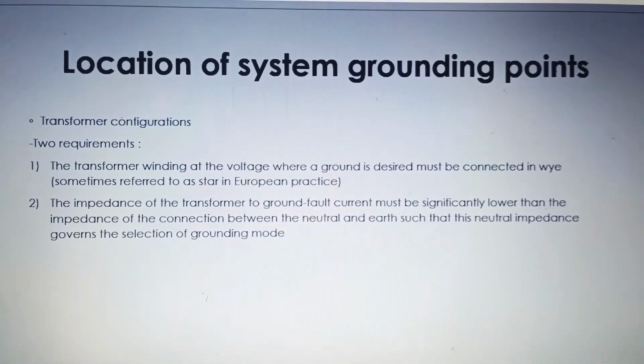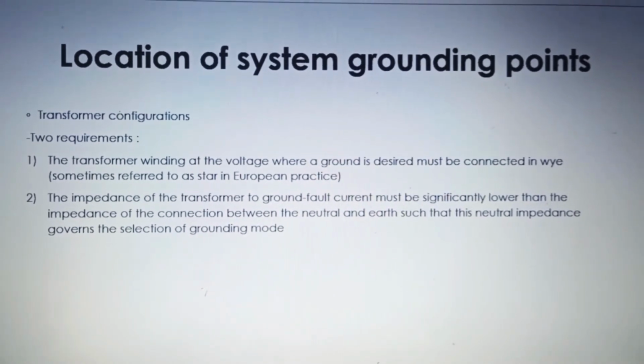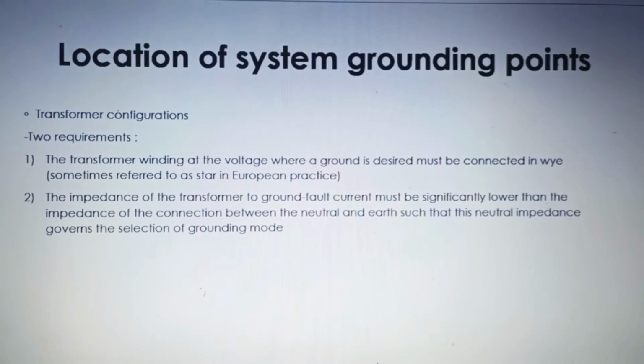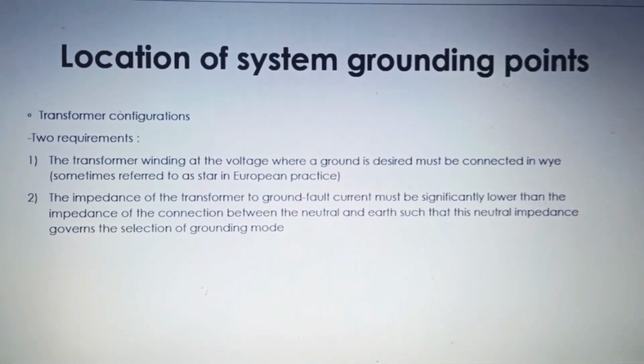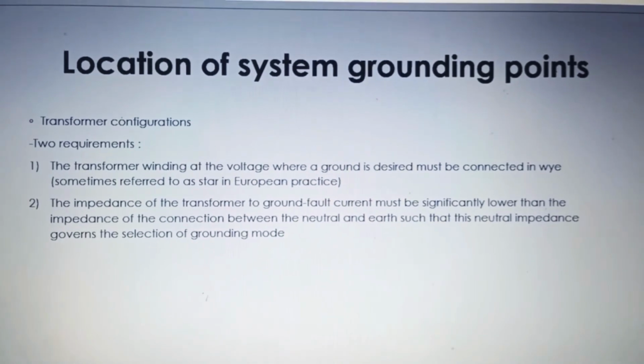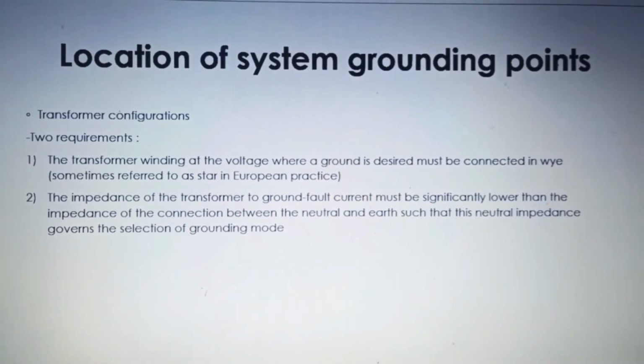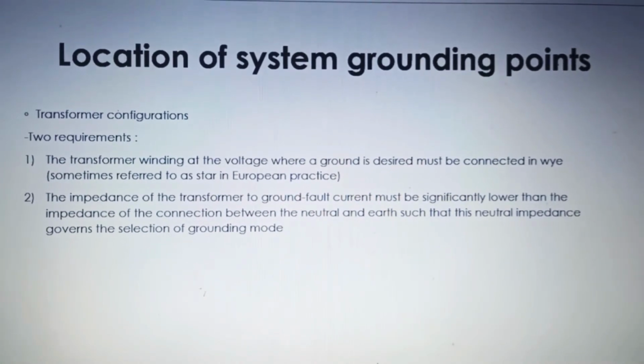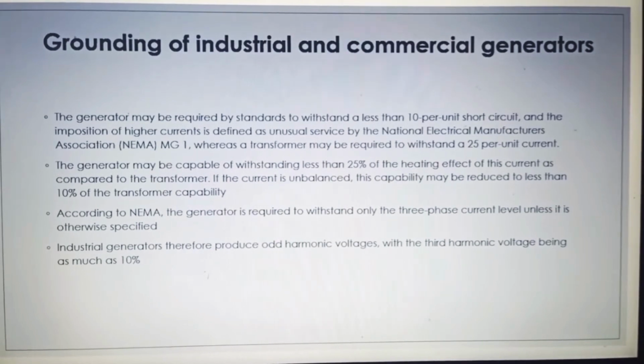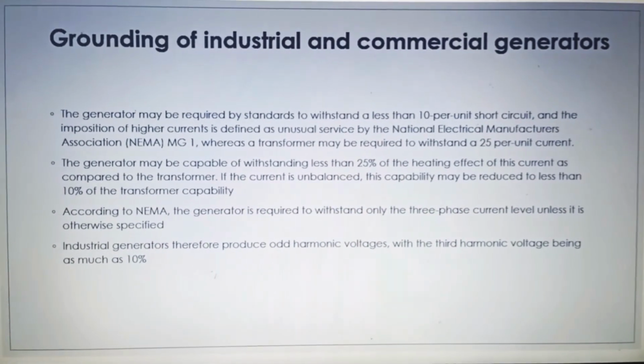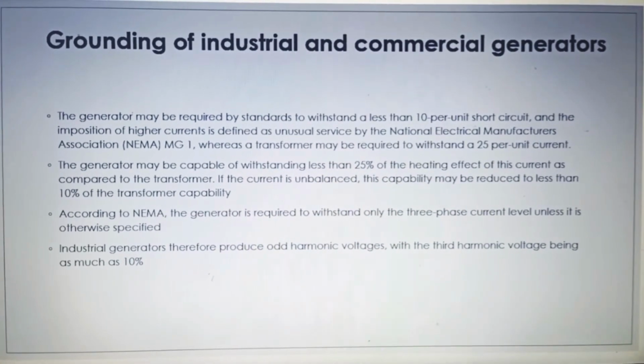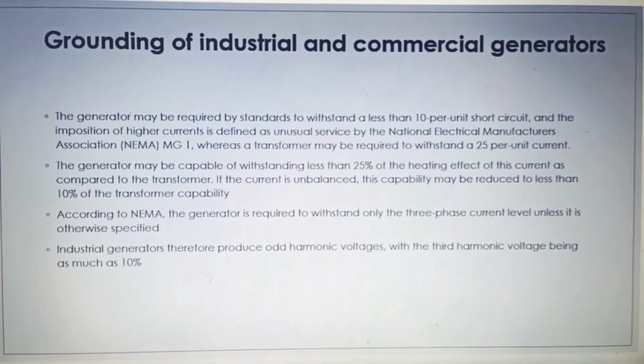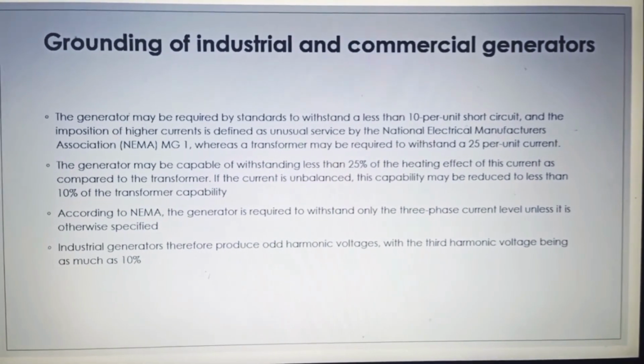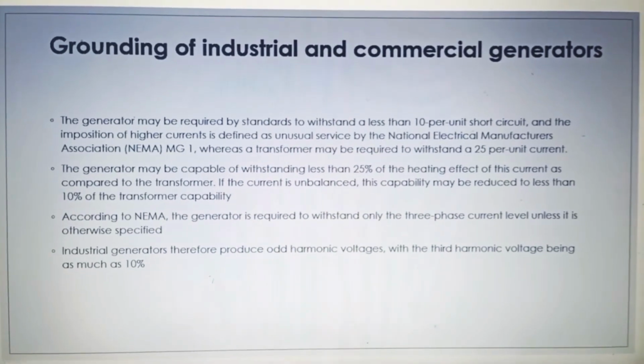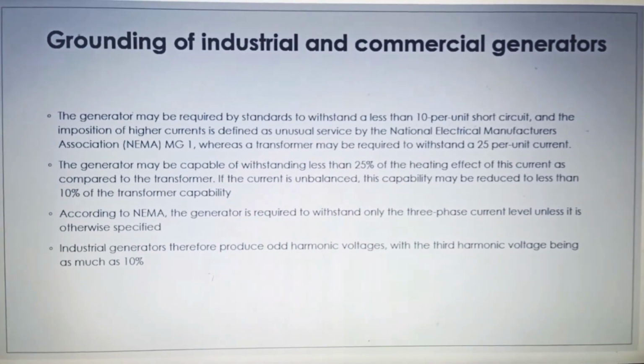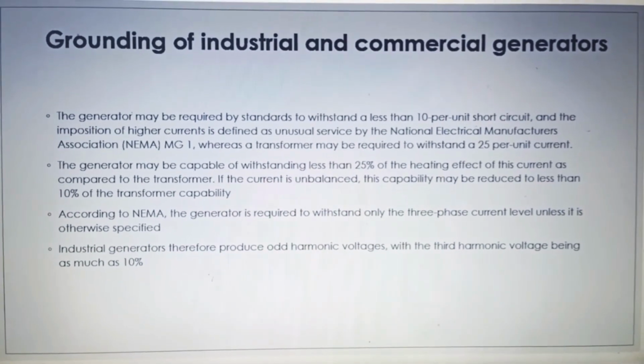The transformer winding at the voltage where a ground is desired must be connected in Y design. The impedance of the transformer to ground fault current must be significantly lower than the impedance of the connection between the neutral and ground, such that the neutral impedance governs the selection of the grounding mode. The generator may be required by standard to withstand less than 10 per unit short circuit, whereas a transformer may be required to withstand 25 per unit current. The generator may be capable of withstanding less than 25% of the heating effect of this current as compared to the transformer. If the current is unbalanced, this capability may be reduced to less than 10% of the transformer capabilities.